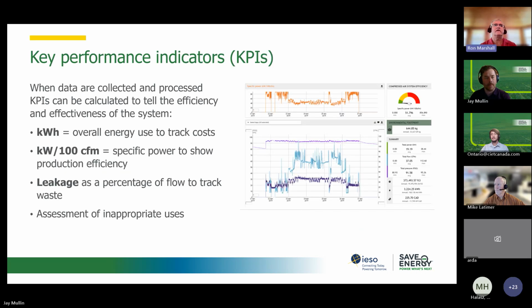Yeah, sure. So these are some of them, and it's not an exhaustive list, right? Key performance indicators that can be calculated or observed from the baseline measurements. Kilowatt hours, of course, help track the costs, but you want to know how efficiently that compressed air is being made, right? Specific power: if you measure the kilowatts consumed by the compressed air equipment and divide it by 100 CFM, that gives us a number that's very commonly used in the industry. I jokingly call it gas mileage, right? Because I can look on my truck, push a button, and see the liters per 100 kilometers.